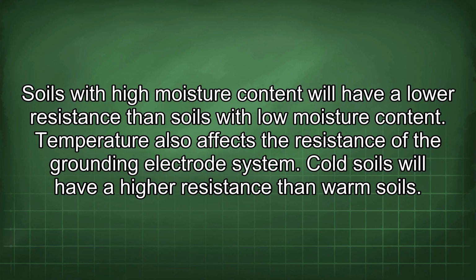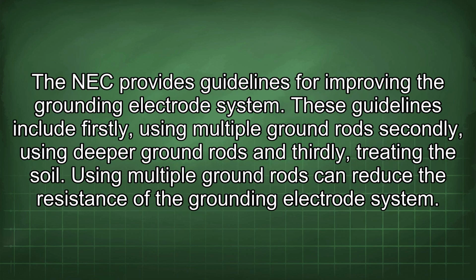Temperature also affects the resistance of the grounding electrode system. Cold soils will have a higher resistance than warm soils. The NEC provides guidelines for improving the grounding electrode system. These guidelines include firstly, using multiple ground rods, secondly, using deeper ground rods, and thirdly, treating the soil.